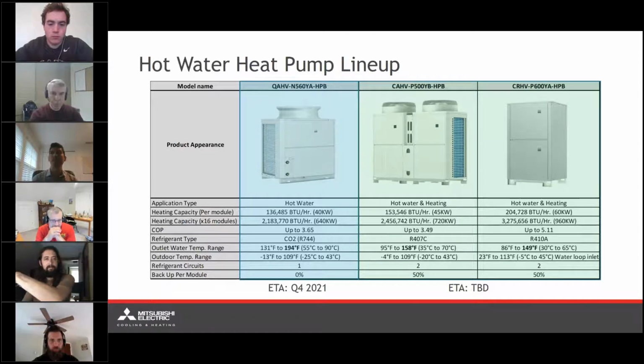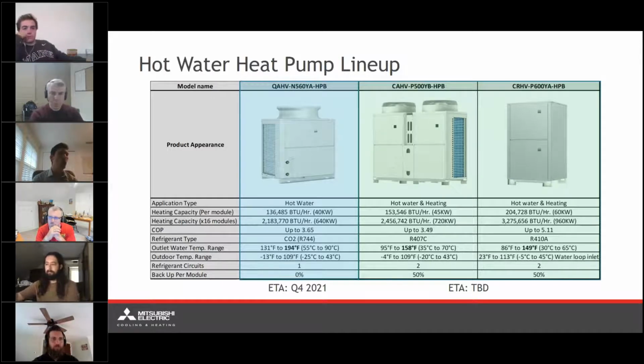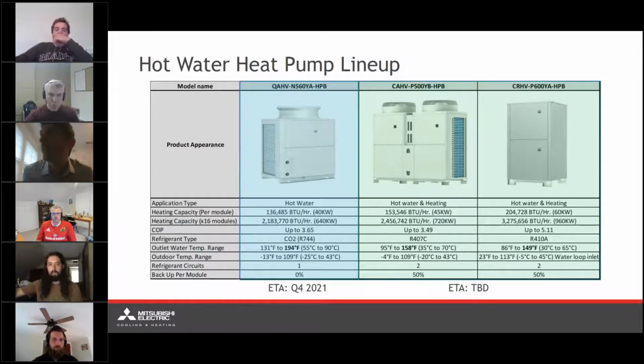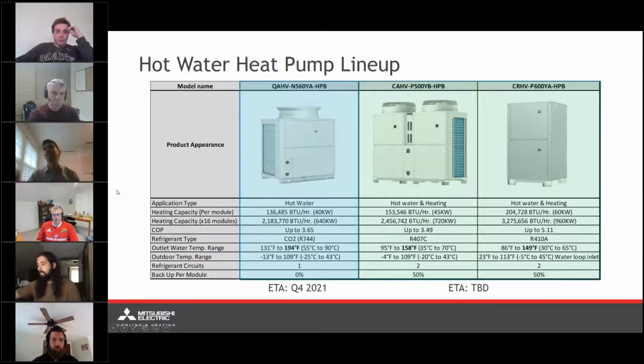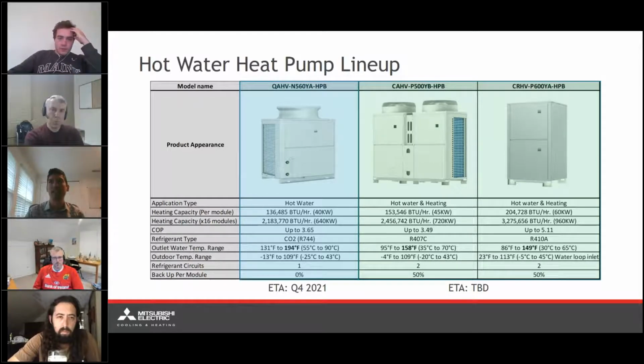So just to give you an idea, this is a self-contained unit. This is only going to have water connections coming out. All the refrigerant within the system itself is located entirely within the condensing unit. And with that said, I just want to point attention to the heating capacities we're looking at here. Per module, each one of these units is going to be capable of just about 10 tons of heating capacity, 136,000 BTUs of heating. And we can actually connect up to 16 of these modules together for up to 2.2 million BTUs of heating capacity.